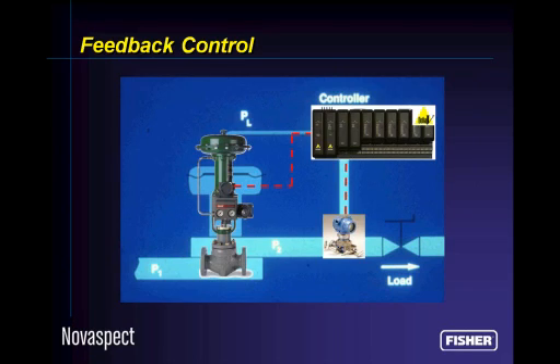Could be a little bit more elaborate, this system. It's still a 3-element control system, but we've got some electronic components instead. You probably would have a Rosemount 1151 differential or pressure transmitter attached to the steam pipe measuring pressure P2. It would send a 4 to 20 milliamp control signal to the, hopefully it's an Emerson DeltaV control system, and that system would be sending out that red dotted line, an electronic 4 to 20 milliamp signal to the valve assembly to position the valve appropriately to get the right pressure.